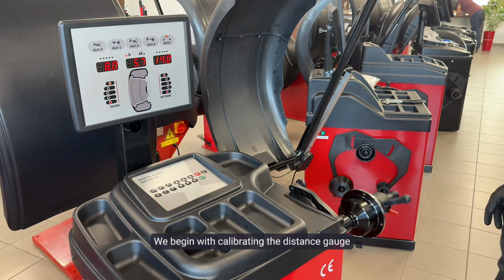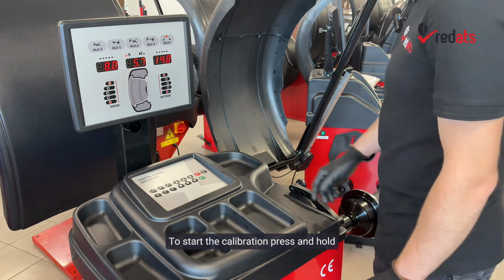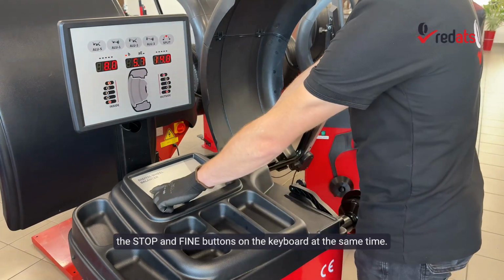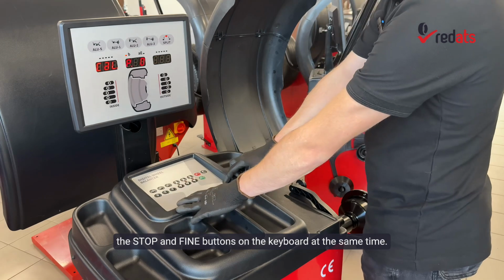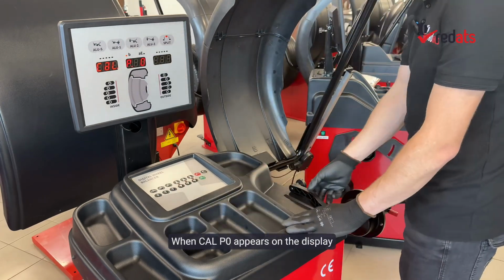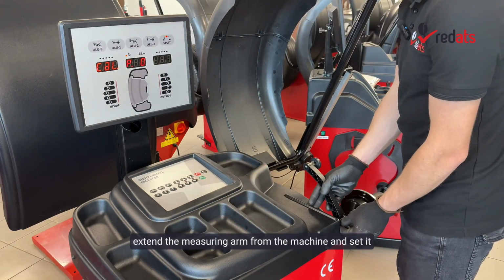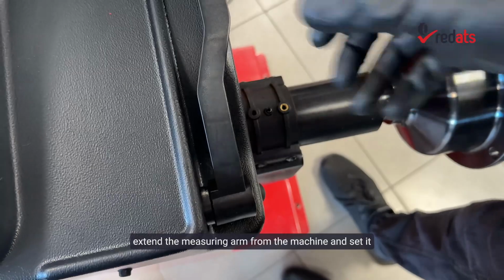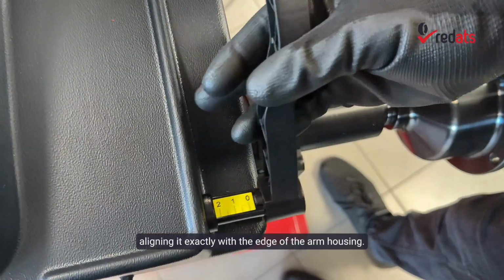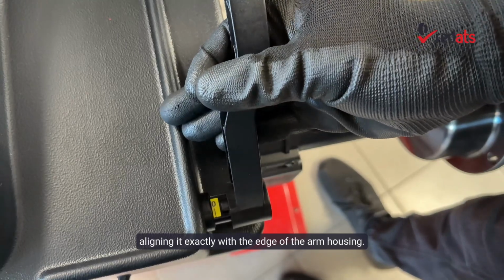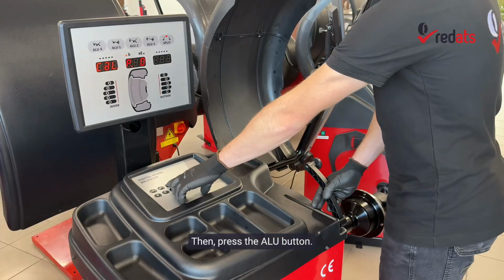We begin with calibrating the distance gauge. To start the calibration, press and hold the stop and fine buttons on the keyboard at the same time. When Cal P0 appears on the display, extend the measuring arm from the machine and set it to the 0 centimeter position, aligning it exactly with the edge of the arm housing. Then, press the ALU button.